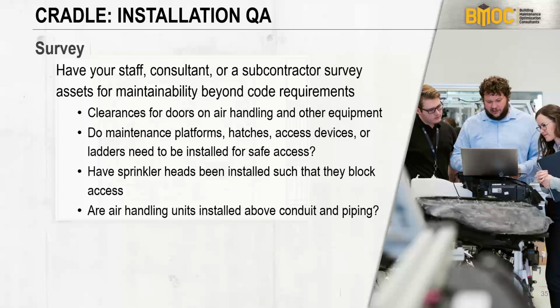Next one: air handling units installed above conduit and piping. I've got a particular image in mind of a unit about 4 feet above the ceiling grid, in a narrow hallway, like a utility corridor in a research lab. We popped the ceiling tile and it was 95% obstructed by utility piping, IT raceway, sprinkler pipe, and anything else you can think of. We couldn't find the unit. We searched all over the place for it, had already looked above the ceiling, and then finally found it.